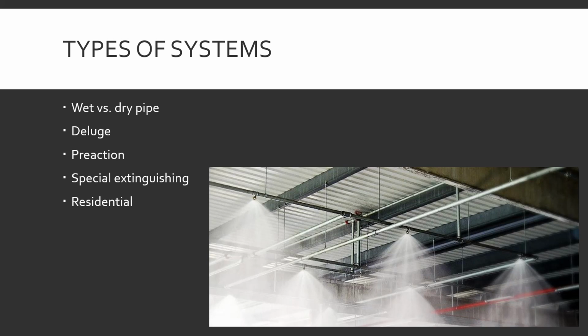With the clean agent ones, it replaces oxygen. So if you go in there, fire or not, you open the door and you're like, nothing in here. You go in, there's no oxygen because the system's gone off. You and whoever else isn't in the pack pile up on the floor because you don't have any oxygen going to you. Well, those ones, whether it's like, oh, we know it's a false alarm, or you don't, pack up on those. And then residential.